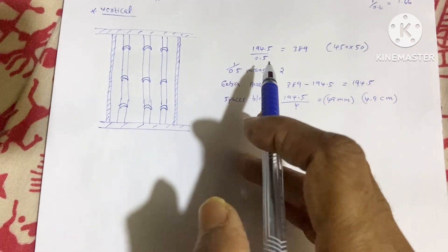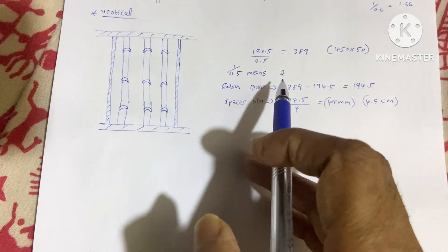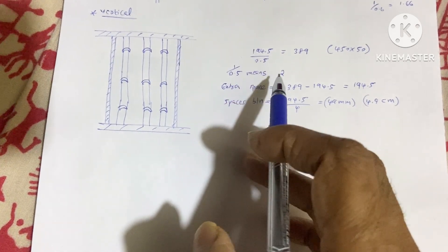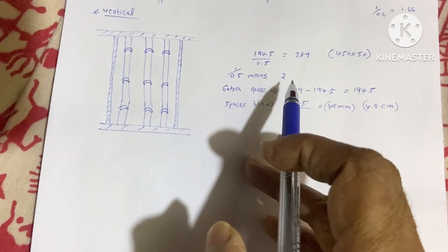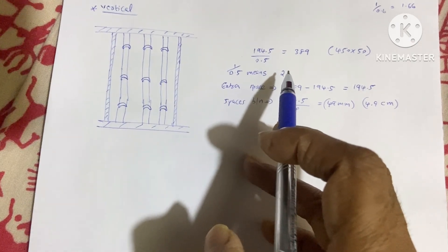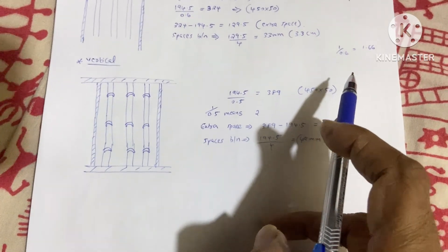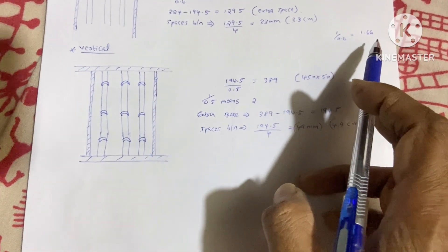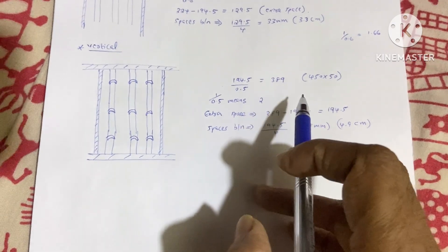Using a factor of 0.5 means we are multiplying by 2, which equals 200% — meaning we are giving 100% extra space. In comparison, the horizontal calculation gave 66% extra. So the vertical tray calculation provides significantly more extra allowance.